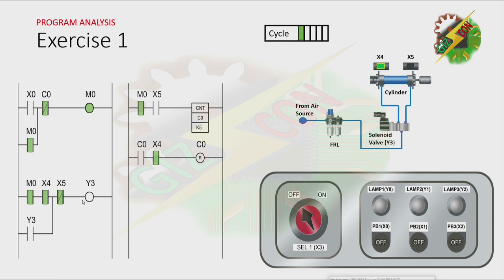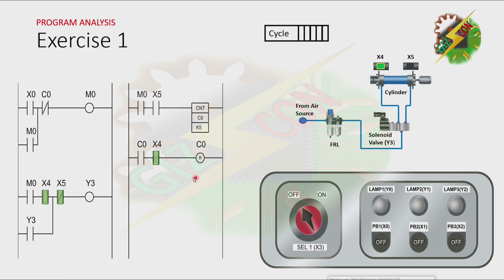Now let's assume that 5 cycles are already complete. Because of that, it will cause counter 0 to turn on. And when the cylinder is at the fully retracted position, it will automatically reset the counter and cause M0 to turn off, breaking the latching. Because M0 is off, the normally open contact of M0 will turn off, and the cycle will not repeat anymore. And because the counter is already reset, the normally closed contact of the counter will go back to its initial state.